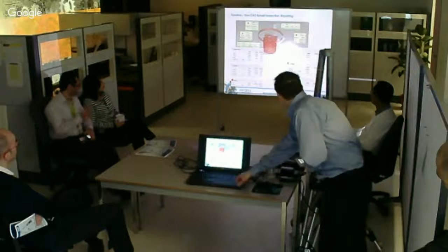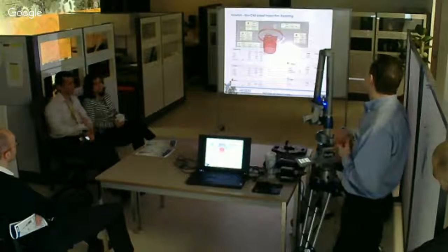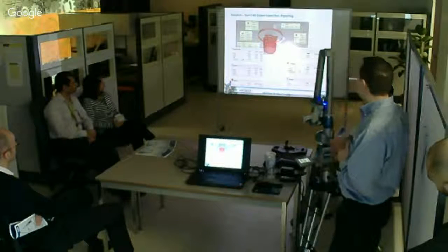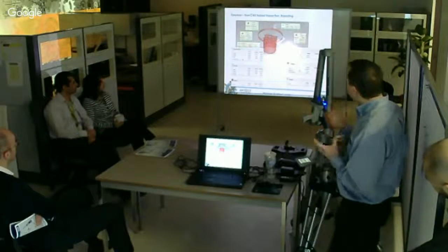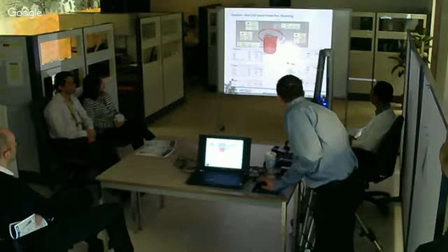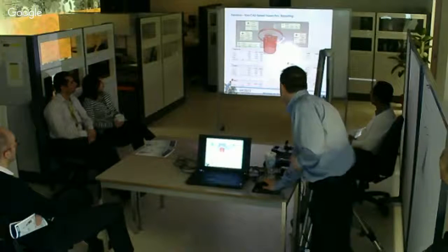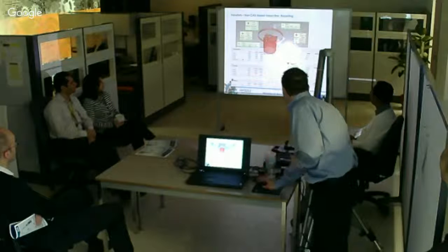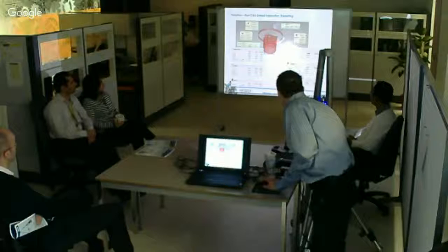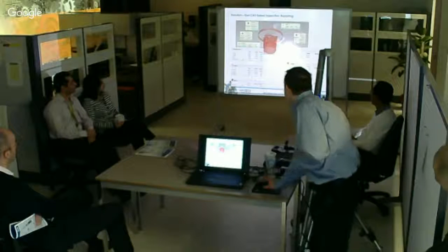It also brings in all your GD&T information. If you don't have CAD, you're still able to do your measurements, circles, cones, lengths, etc. from the arm itself. As you can see, it's created cylinders, cones, and circles here from the probe tip measuring. It still gives you a report, obviously not comparing to nominal data, but still giving you plane-to-plane comparison, cylinder information, concentricity, perpendicularity, length, etc.